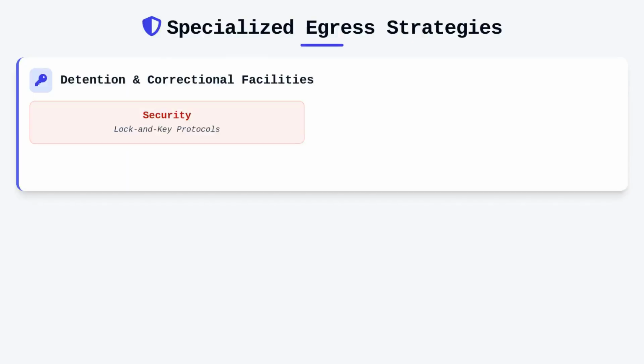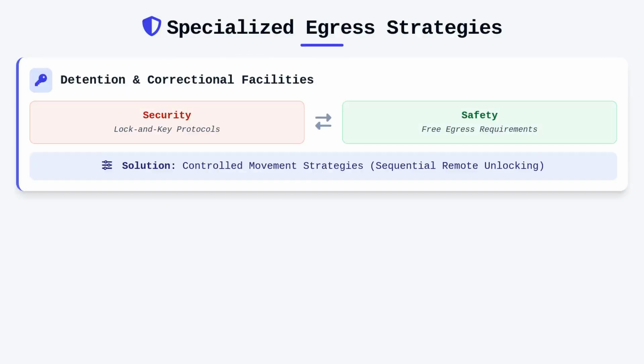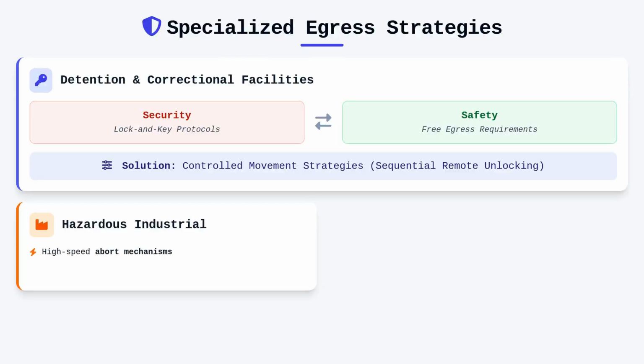We also confront the binary conflict between security and safety in detention and correctional facilities, where lock and key protocols are inherently opposed to the free egress requirements of the code. In these environments, we utilize controlled movement strategies where staff can remotely unlock specific doors in sequence to guide occupants to secure zones. Moving into hazardous industrial environments, we require high-speed abort mechanisms and emergency egress pathways that are shielded from the specific threat, such as chemical spills or deflagration zones.